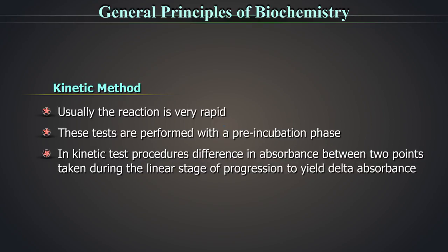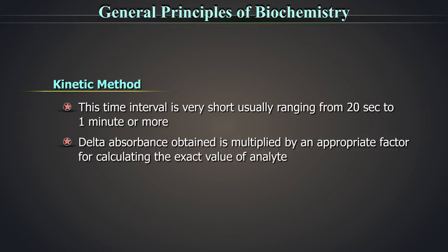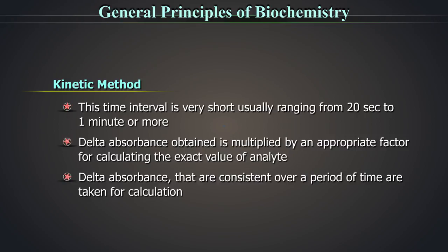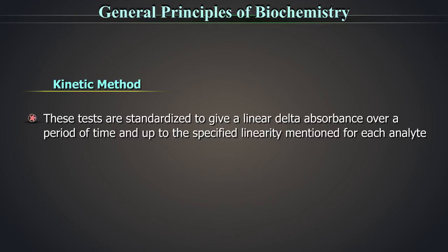In kinetic test procedures, the difference in absorbance between two points taken during the linear stage of progression of the test is taken into consideration to yield the delta absorbance. This time interval is very short, usually ranging from 20 seconds to 1 minute or more. The delta absorbance obtained is multiplied by an appropriate factor for calculating the exact value of analyte. The delta absorbance that are consistent over a period of time are taken for calculation. These tests are standardized to give a linear delta absorbance over a period of time and up to the specified linearity mentioned for each analyte.